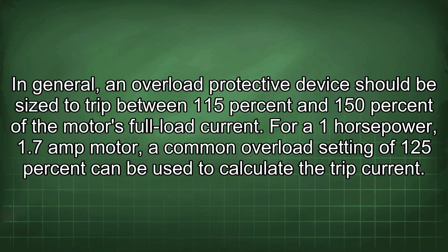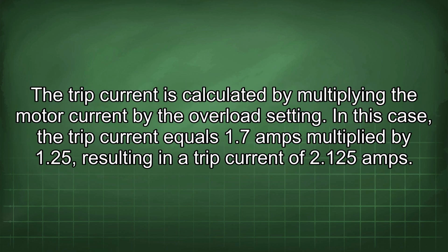In general, an overload protective device should be sized to trip between 115% and 150% of the motor's full load current. For a 1 horsepower, 1.7 amp motor, a common overload setting of 125% can be used to calculate the trip current. Trip current is calculated by multiplying the motor current by the overload setting. In this case, the trip current equals 1.7 amps multiplied by 1.25, resulting in a trip current of 2.125 amps.